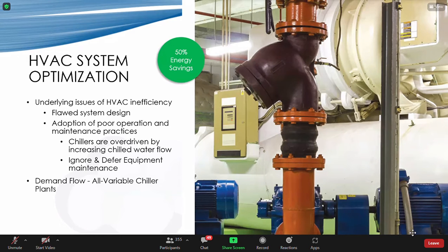As I mentioned, the solution there is demand flow—make your chiller all variable. From the special, showing a hydronic system using water to cool the system. These are mostly used in bigger buildings. It really saves you a lot, and you've got to use new technologies for these types of systems. So it's important, as an engineer, to look at optimizing the HVAC system.